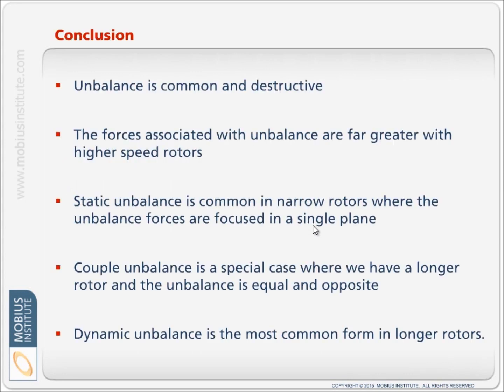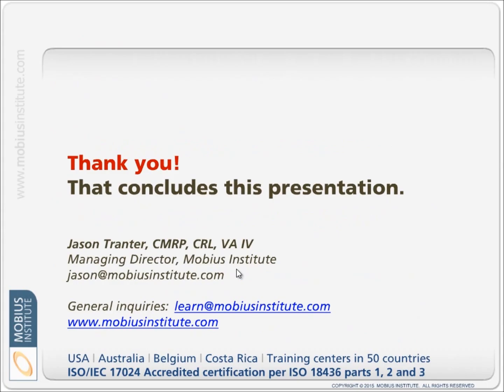In conclusion, unbalance is common — more common in some machines than others — and it is destructive. The forces associated with unbalance are far greater with higher-speed rotors. Static unbalance is common in narrow rotors where the unbalanced forces are focused in a single plane. Couple unbalance is a special case with a longer rotor where the unbalance is equal and opposite at each end. Dynamic unbalance is the most common with longer rotors, where the unbalanced forces are not equal at either end and not exactly opposite each other. I hope this presentation has helped clarify a few points associated with unbalance — thank you for viewing.